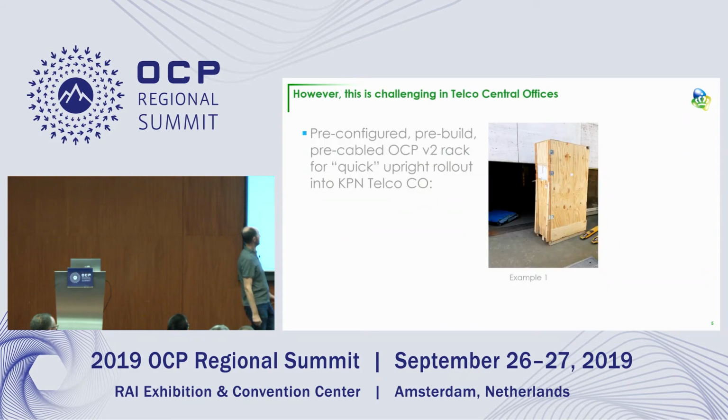However, this was one of the racks which arrived at one of my test facilities, a normal V2 rack. And as you can see, it won't fit. And this is the loading bay at the back of the building. So getting this guy upright into this building, that might be somewhat challenging.